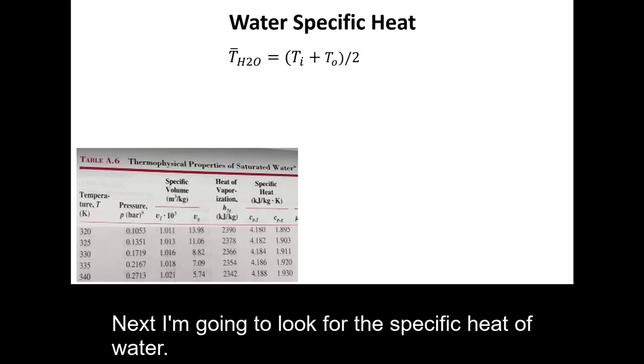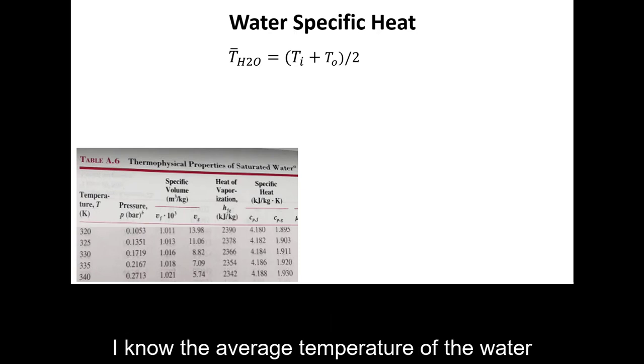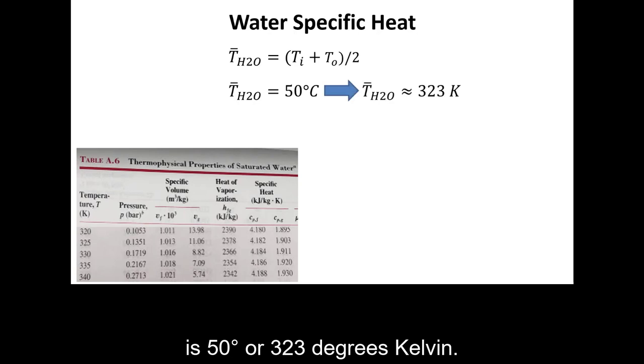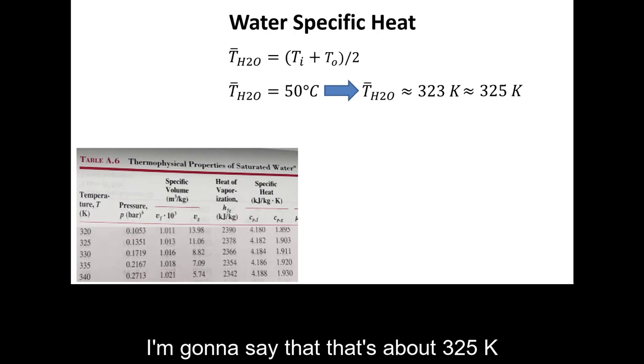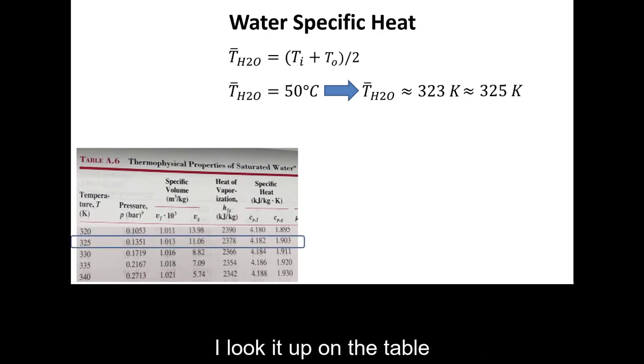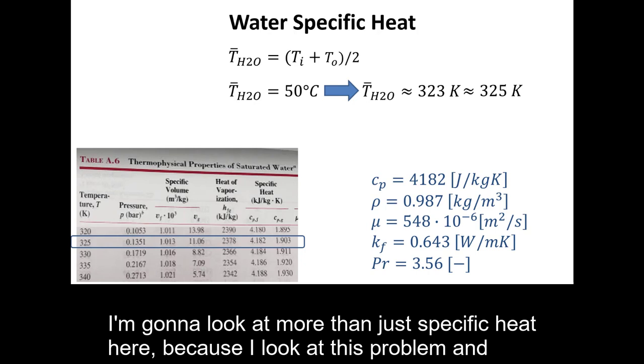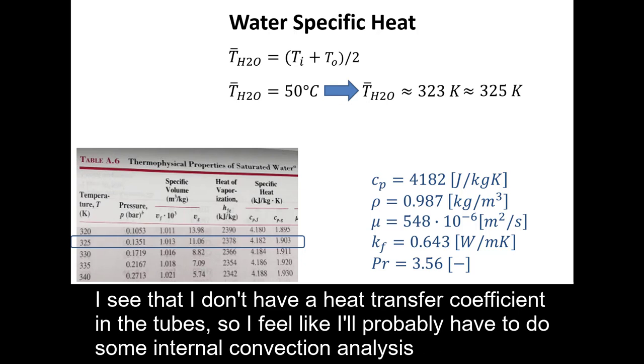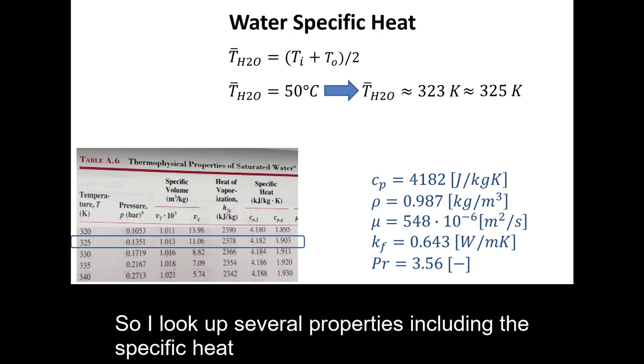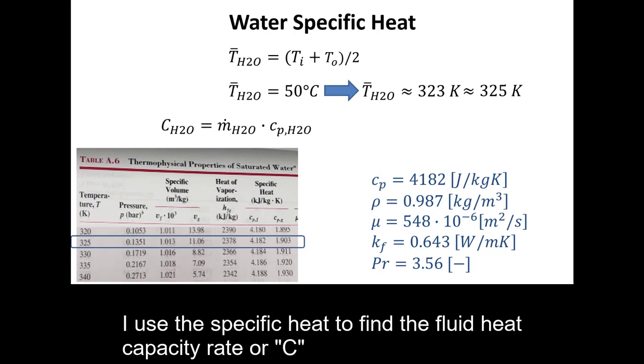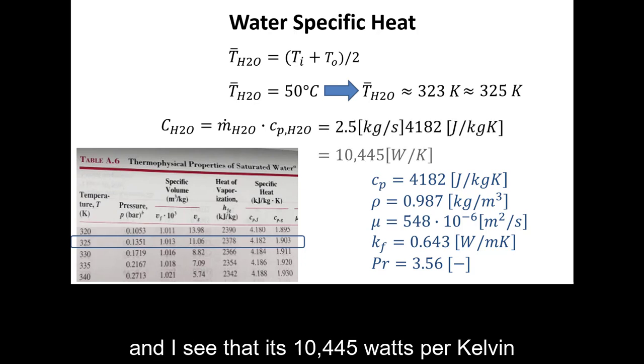Next I look up the specific heat of water. The average water temperature is 50 degrees Celsius, or 323 Kelvin, which I round to 325 Kelvin. I look up several properties — not just specific heat — because I notice the problem doesn't give a heat transfer coefficient inside the tubes, so I'll likely need to do an internal convection analysis. Using the specific heat, I calculate the fluid heat capacity rate on the cold side, capital C_cold, and find it is 10,445 watts per Kelvin.